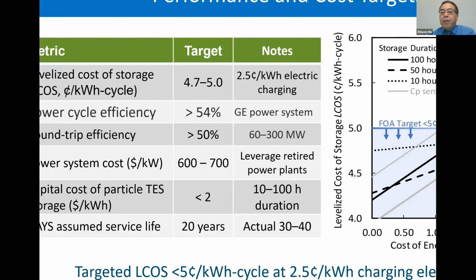The difference between long duration storage and, say, 10-hour storage is that there are fewer cycles per year, so there are fewer chances to recover the profit and earn revenue. Therefore, it's more sensitive to the capital cost of the power system and the storage system. But for low storage hours, it's fairly less sensitive because it will cycle more. So we see our path starting from current needs for shorter storage, and with technology development and economic need, moving to longer storage applications. And this also illustrates what Engine showed, that the decoupling of power from duration is something thermal energy storage can do well.